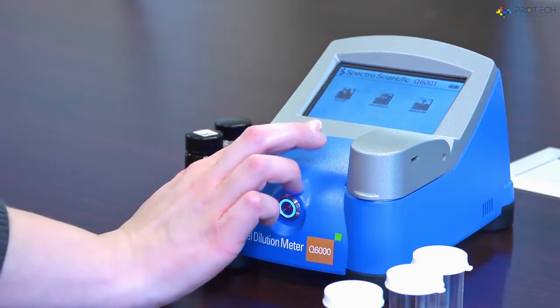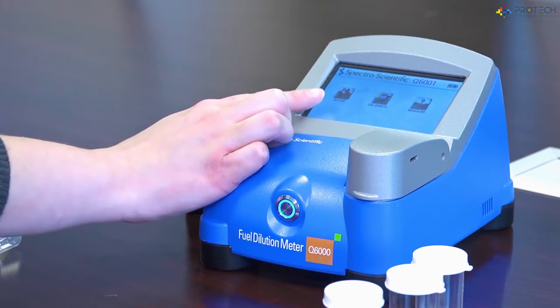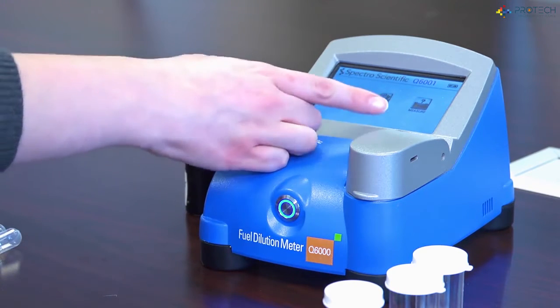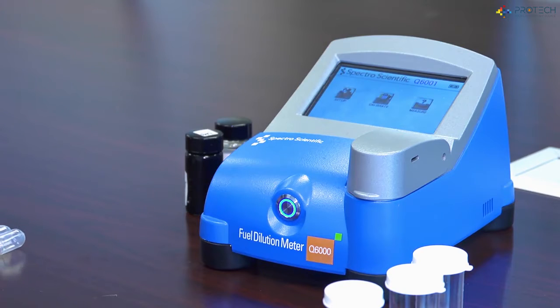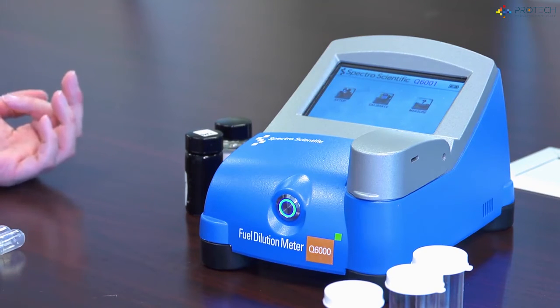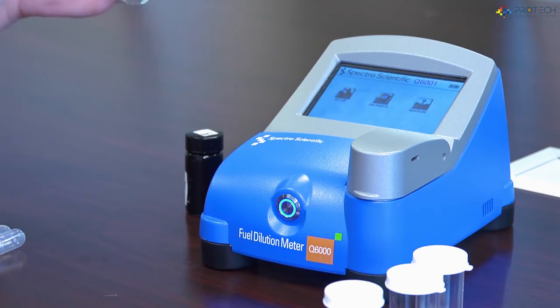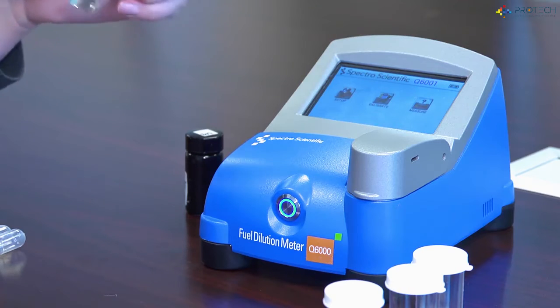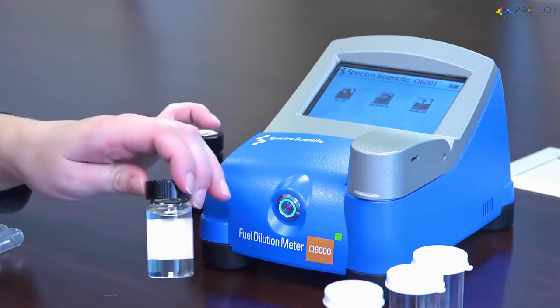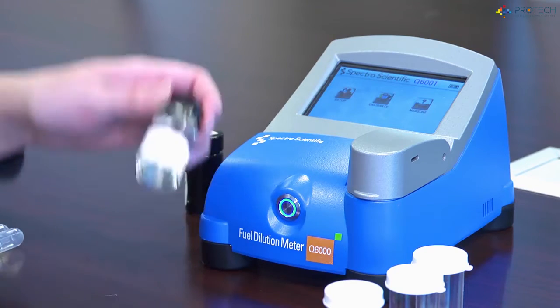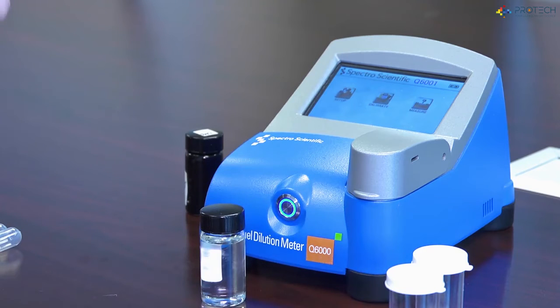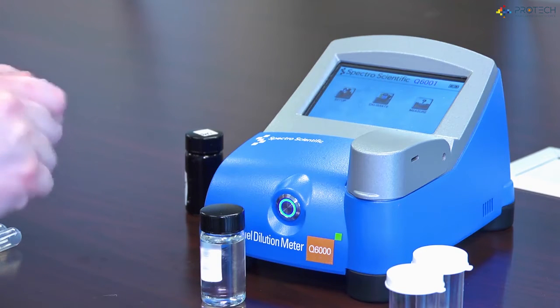So on the screen you have 3 buttons. The first is setup, the second is calibrate, and the third is measure. The first thing that you're going to need to do is calibrate the instrument, and you're going to want to calibrate with the specific blend and type of oil that you're using in your samples and your blend of fuel. So I have a 5% diesel standard here, and I'm going to prepare a sample vial.